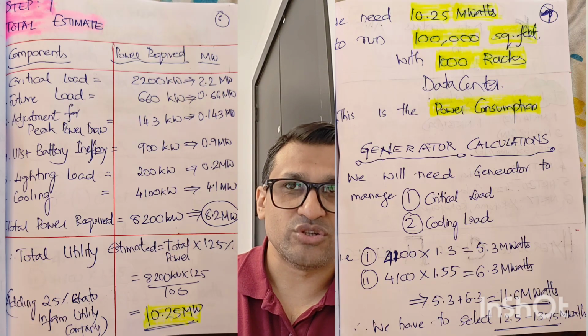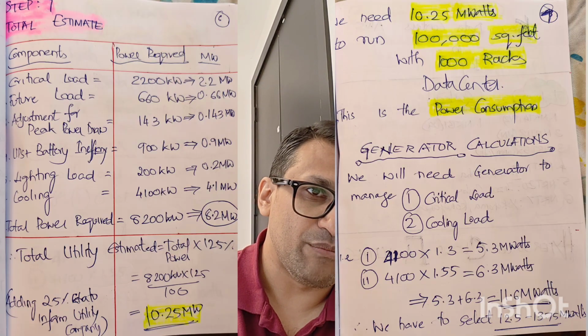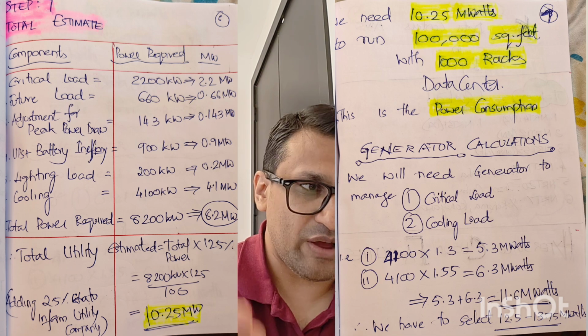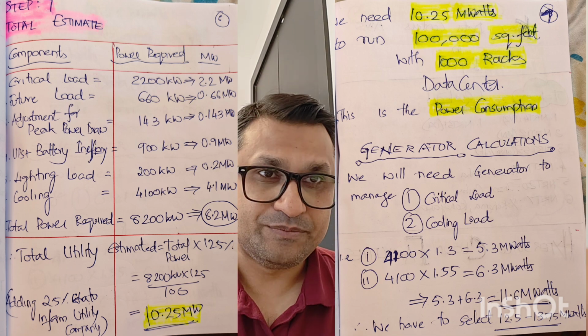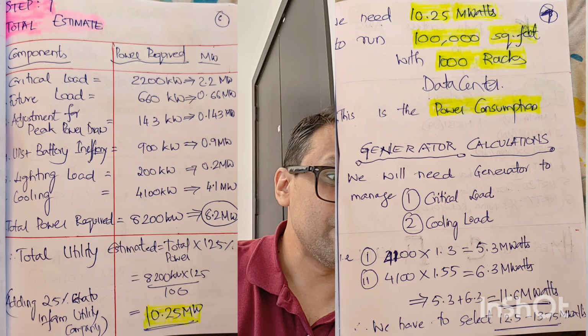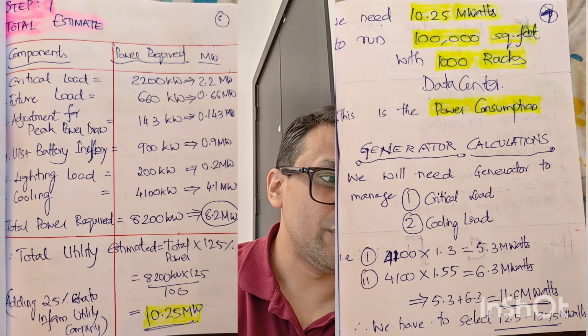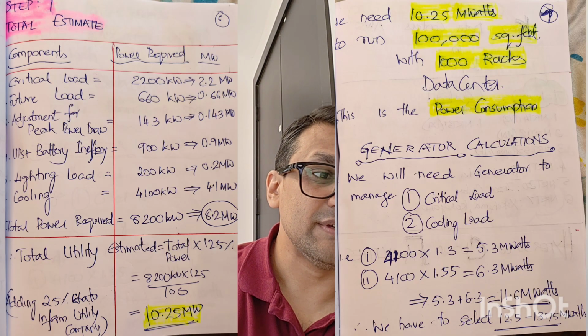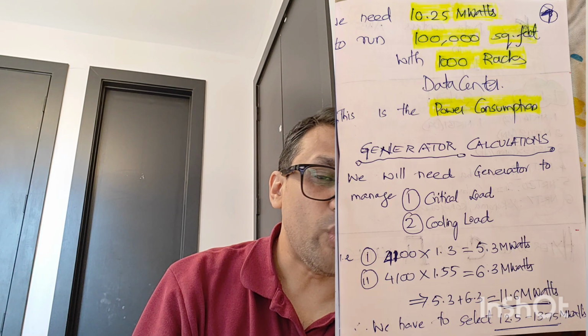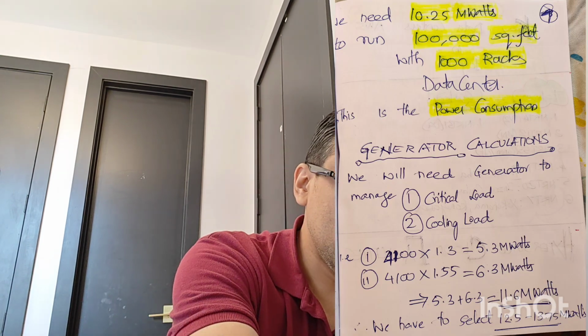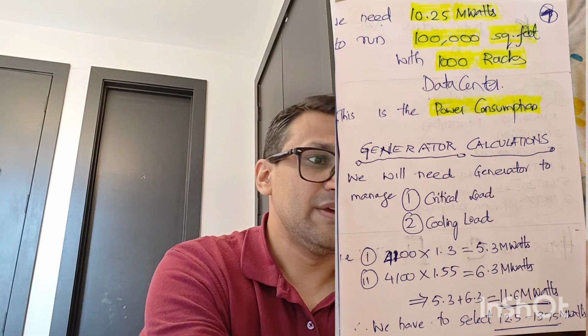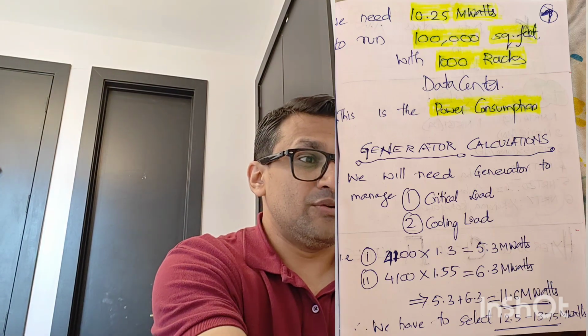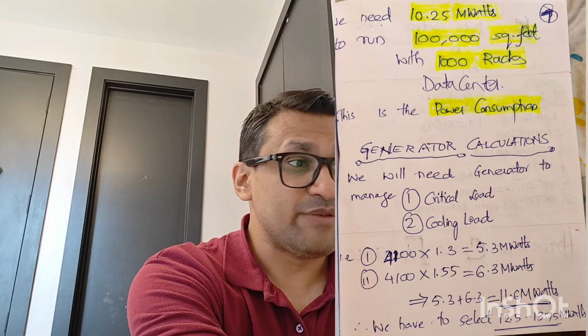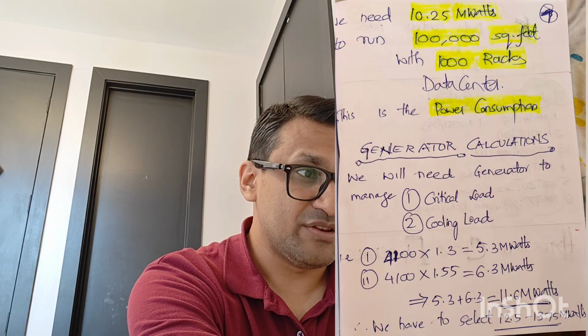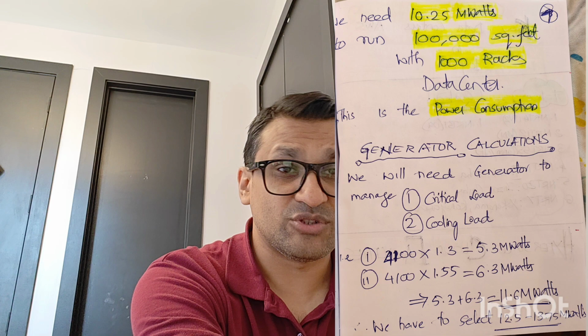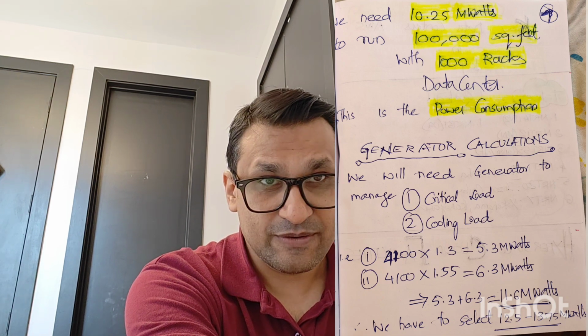So originally we got 8.2, but when you are designing and requesting power from the utility company, you need 10.25 megawatt because you are adding 25% extra. So when you tell them, you need 10.25 megawatt to run a 100,000 square feet data center with 1,000 racks. This is the power consumption. So that's the power requirement for 100,000 square feet. That's a basic design.